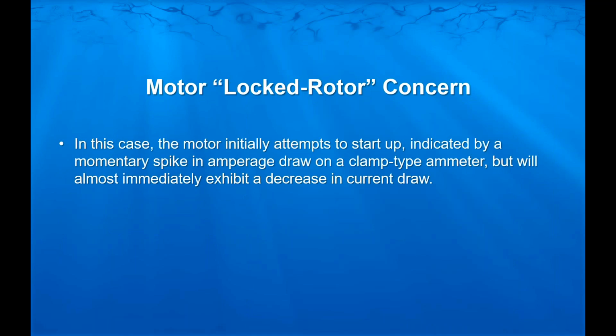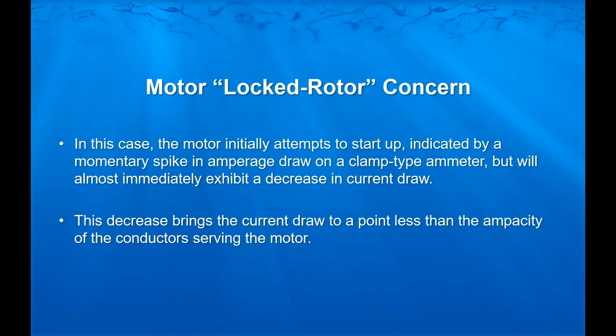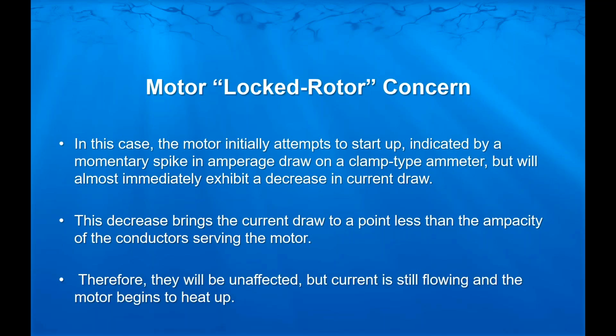In this case, the motor is going to initially try to start up, which, if you had a clamp meter on the wiring, you would see an initial spike in the amperage draw. But that draw is almost immediately going to decrease. That decrease brings the current draw lower than the ampacity of our conductor and obviously lower than the overcurrent protection if we rated it at 150% of the conductor. Neither of those are going to be affected, and the current's still going to flow, and the motor is going to start to heat up.